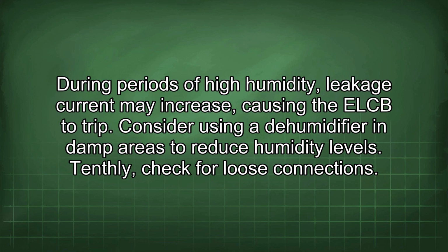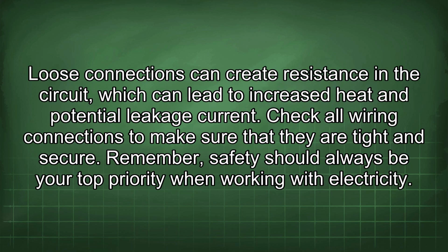Tenthly, check for loose connections. These connections can create resistance in the circuit, which can lead to increased heat and potential leakage current. Check all wiring connections to make sure that they are tight and secure.